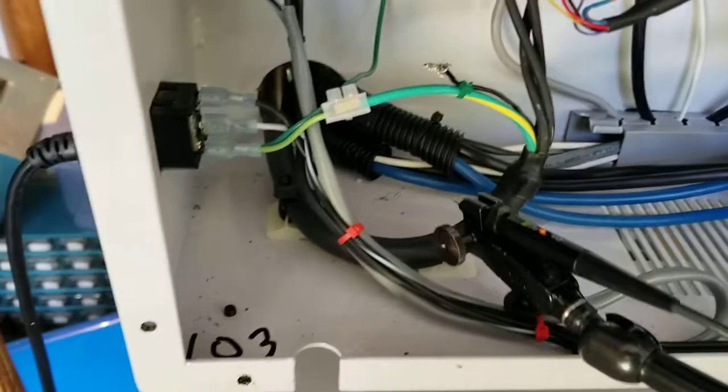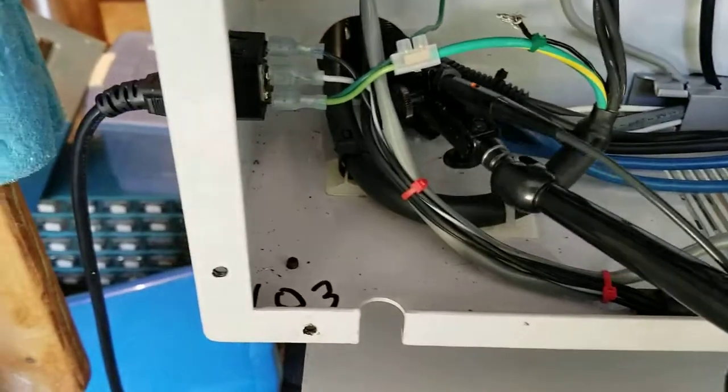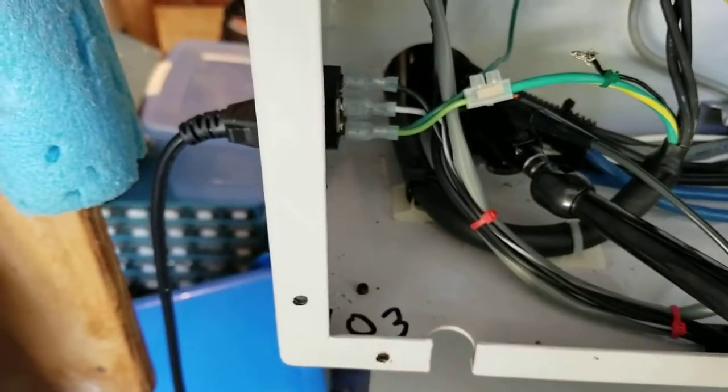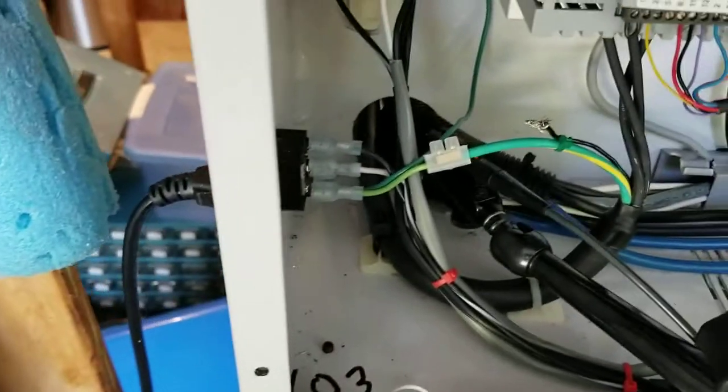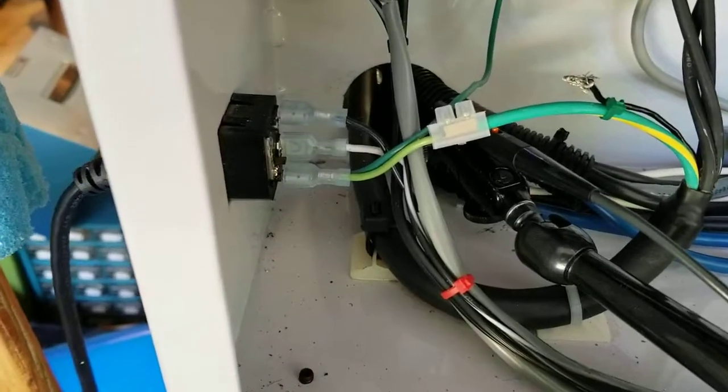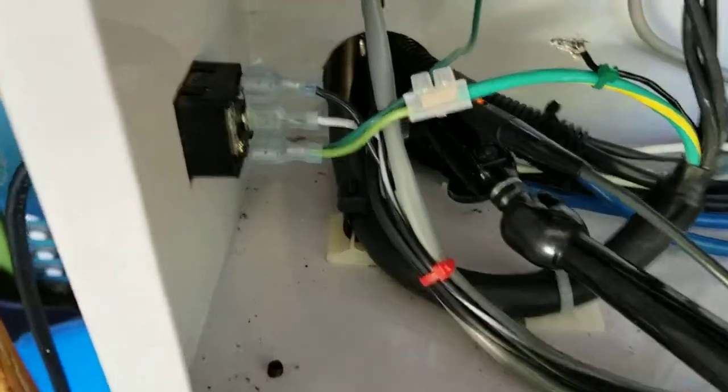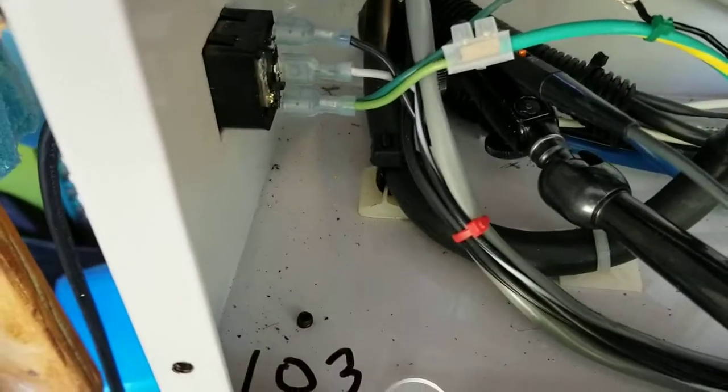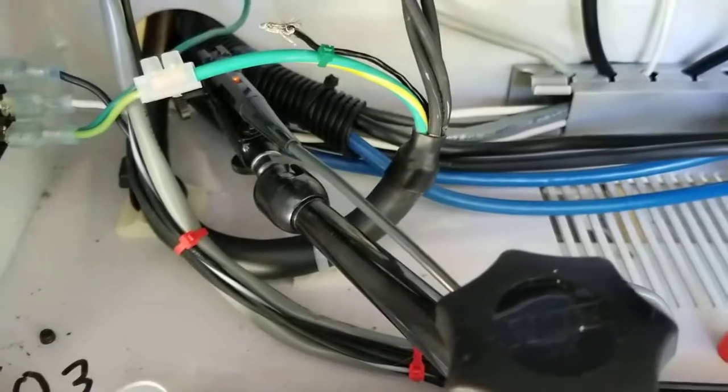Now, a real major concern is what about all those signal cables that get run at least a short distance alongside the VFD cable. So here I put my probe right on the outside of the plastic jacket that contains all the signal cables for the drives.